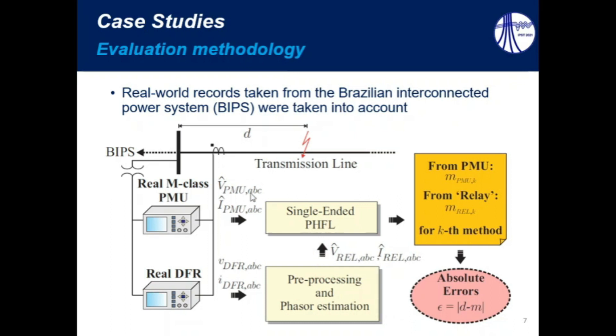Then, since PMU phasors and relay phasors are obtained, we apply single-ended phasor-based fault location methods, resulting in the estimations m-PMU and m-relay. And finally, we calculate the absolute error, considering the absolute value of the difference between the estimated fault distance and the fault distance reported by line inspection crews for each analyzed case.